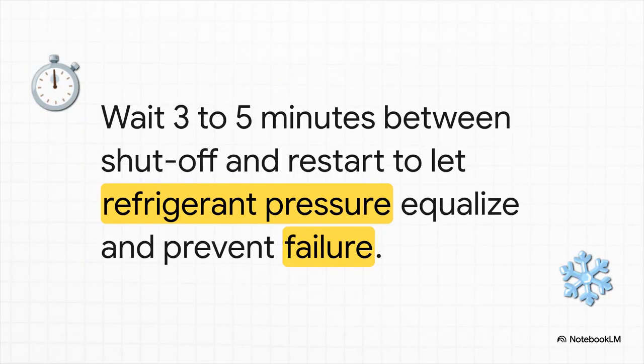Next up is the 3-minute rule. This is a vital habit to prevent your compressor from pushing against high pressure and failing under the strain. You see, when your AC turns off, the refrigerant pressure inside the system is still highly unbalanced. If you force it to restart immediately, which is called short cycling, the compressor has to fight against this immense built-up pressure. Waiting just 3 to 5 minutes allows that pressure to equalize naturally. Ignoring this rule, well, you dramatically shorten the life of your compressor and waste massive amounts of energy.